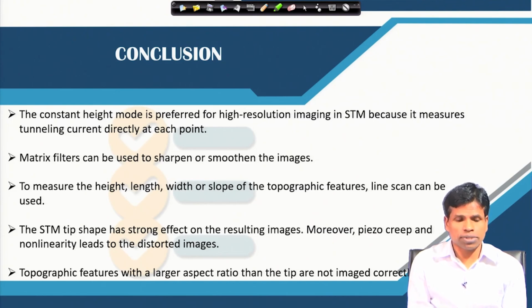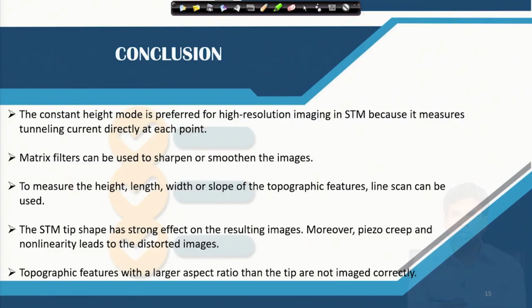As we have also seen, the STM tip has a strong effect on the resulting image. The tip has to be atomically sharp and it has to be a single tip, otherwise a distorted image will form because of the distorted tip. In addition to that, we have piezo creep and non-linearity that also lead to distorted images. For getting information about a larger or high aspect ratio feature, the tip also has to be high aspect ratio to provide the correct image.